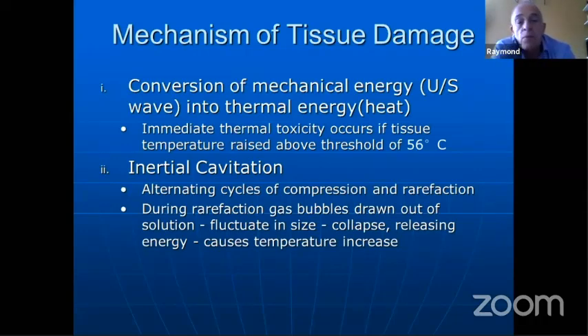The other process by which we get tissue damage is something called inertial cavitation. And what happens is as the ultrasound wave is moving through the tissues, you get alternating cycles of compression and rarefaction. And during the rarefaction stage, gas bubbles are drawn out of the solution. And these gas bubbles will fluctuate in size, eventually getting very large, and then they collapse. And this releases energy, which causes a further increase in the temperature.